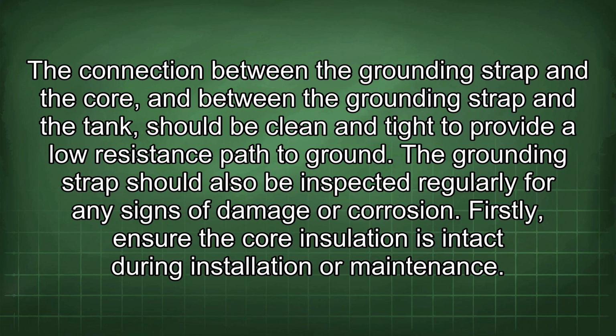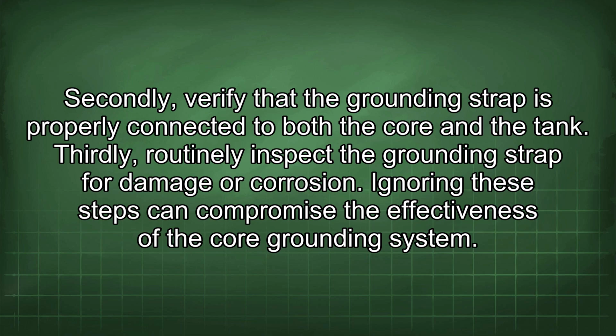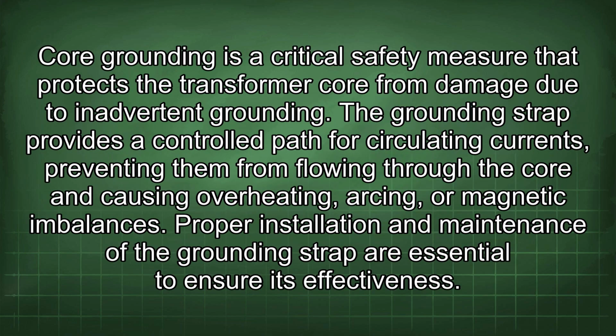Firstly, ensure the core insulation is intact during installation or maintenance. Secondly, verify that the grounding strap is properly connected to both the core and the tank. Thirdly, routinely inspect the grounding strap for damage or corrosion. Ignoring these steps can compromise the effectiveness of the core grounding system. Core grounding is a critical safety measure that protects the transformer core from damage due to inadvertent grounding. The grounding strap provides a controlled path for circulating currents, preventing them from flowing through the core and causing overheating, arcing, or magnetic imbalances. Proper installation and maintenance of the grounding strap are essential to ensure its effectiveness.